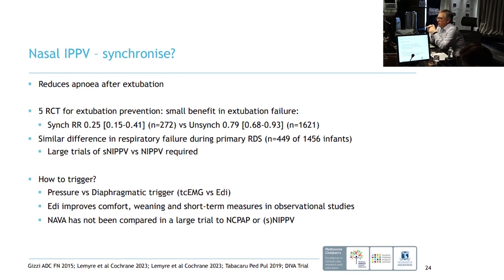How does a ventilator know a baby's breathing? With an intubated patient, they generally use a flow sensor to measure gas movement. You can't do that with a baby on non-invasive support because you've got a huge leak and lose a lot of stability. So whilst people do it, it's not generally the way you should do it. Most synchronised systems instead use a pressure trigger, where you set the sensitivity of pressure change required. I always start the pressure trigger really high and then move it down.